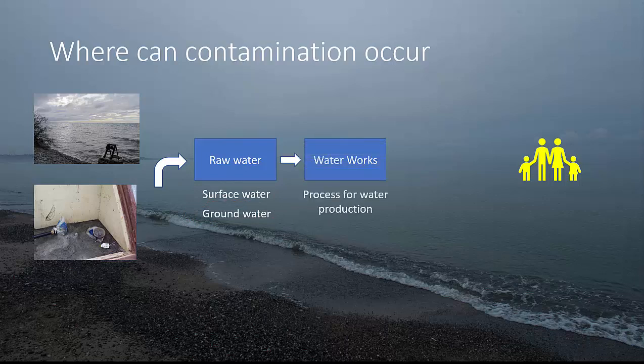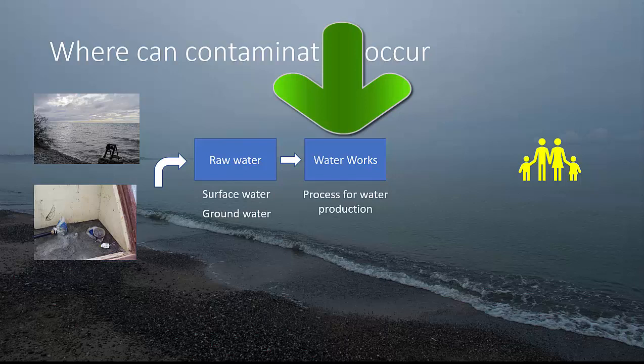Now let's go to the waterworks. Here we have several different treatment methods: flocculation, sedimentation, sand filtration. You can have membranes such as ultra filters, nano filters, or reverse osmosis membranes. You can have ozone, carbon filters, and slow sand filtration. There are many different types of unit operations that can be combined with each other, so there's a multitude of different setups. Within the waterworks you can also have contamination, but this is the place where you can really stop the contaminants — it should remove everything you don't want in the drinking water.